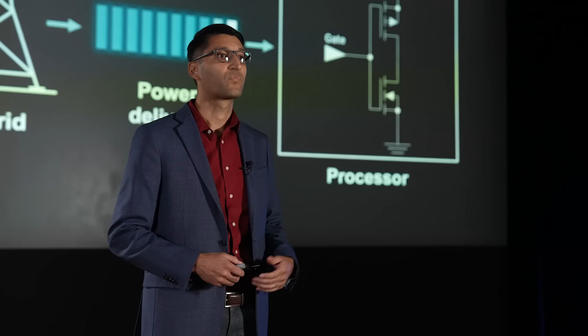Add to that the desire to increase the number of processors in an IT rack. This reduces latency in these large AI models and requires an increase in compute density. So the result is that what used to be tens of kilowatts in IT racks is going to quickly move to over 100 kilowatts, and in the not too distant future, over 1 megawatt per rack. Now, when we add this all up at the data center level, the tens of megawatts for a typical data center today quickly becomes hundreds of megawatts and will soon be greater than a gigawatt of power consumed in future AI data centers. This is an orders of magnitude increase in power consumption and compute density, and the impact is dramatic.